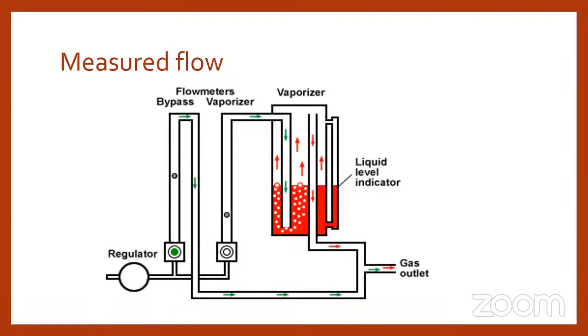And the second one is the measured flow vaporizer. It contains basically a vaporizer with two sets of tubing. One is for the fresh gas, and the second one is for the outlet. It has a regulator at the machine end, so that we can measure and regulate the flow of fresh gas which can be entered into the system.